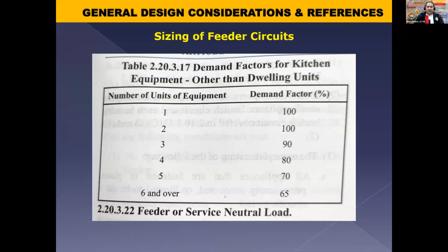Okay, good question, no? Kung sa mixed use, saan mag-govern yung demand factor? Actually, sir, i-separate mo talaga yan for mixed use. Separate demand factor for dwelling, separate demand factor for commercial. And then you combine that, no, dun sa main.